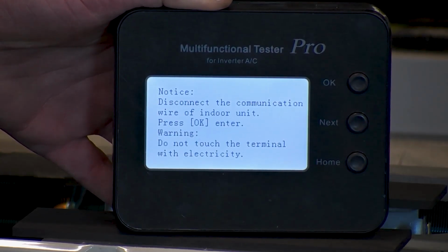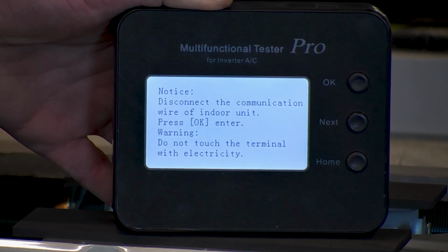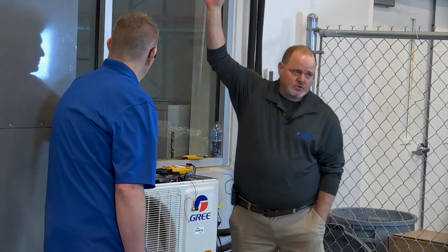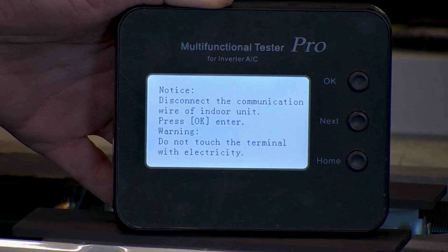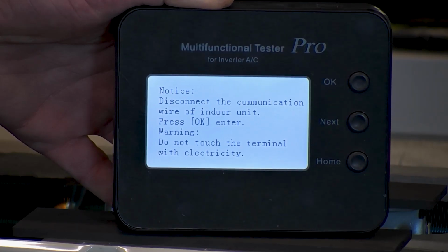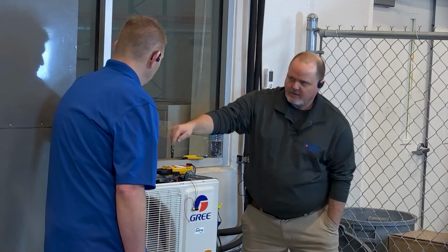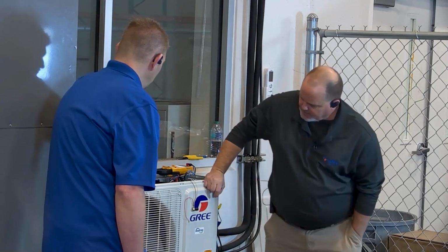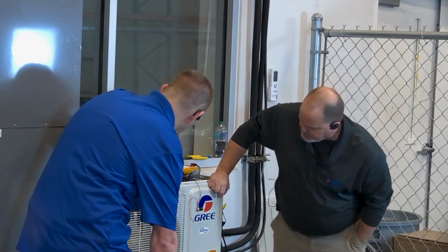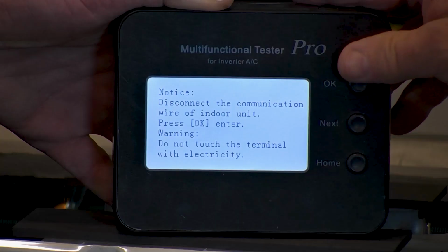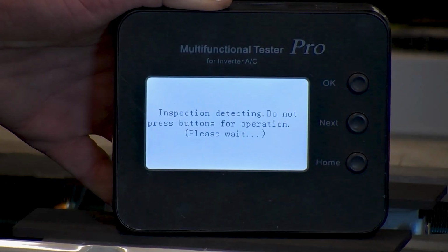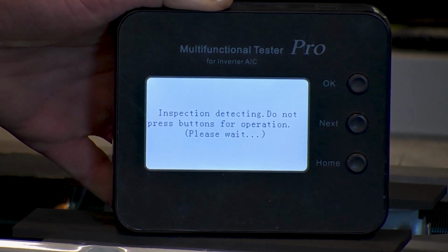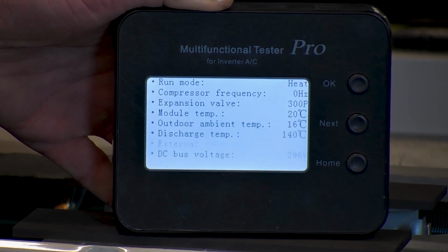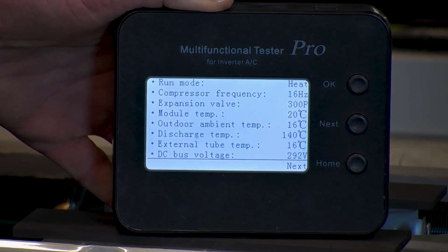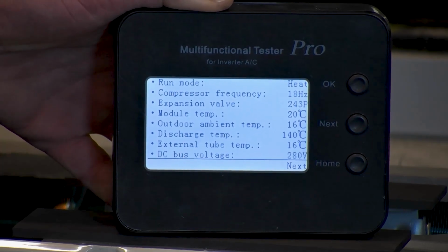So now, this indoor unit still has power going to it, but it doesn't have communication to it. The communication is from this service tool to the outdoor unit. It's going to simulate that it has an indoor unit. Oh, you've got to hit OK. Sorry, we missed a step. Yep. So now it's detecting, reading all the sensors. And there's all your sensor readings. There you go. We are not hooked up to an indoor unit.